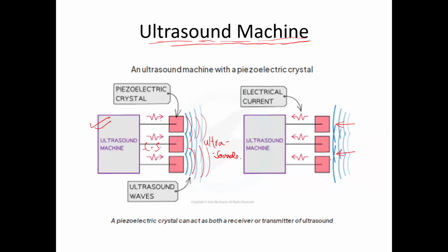The piezoelectric crystal also absorbs the ultrasound and converts it into an electrical signal. So this piezoelectric material has the capability of doing both. The ultrasound machine can give out electrical signals and can receive electrical signals. This is just a simple description. The piezoelectric crystal can convert the given electrical signals into ultrasound pulses, and convert ultrasound signals into electrical pulses. Is this fine?